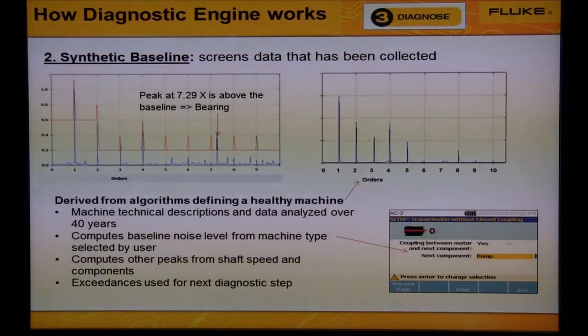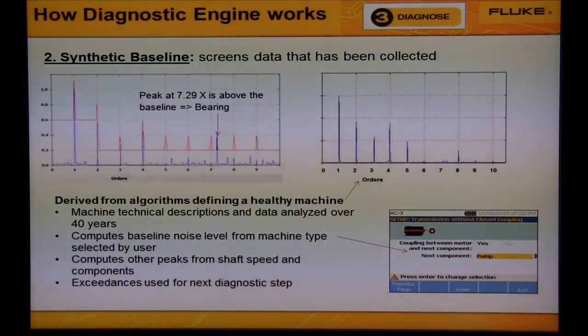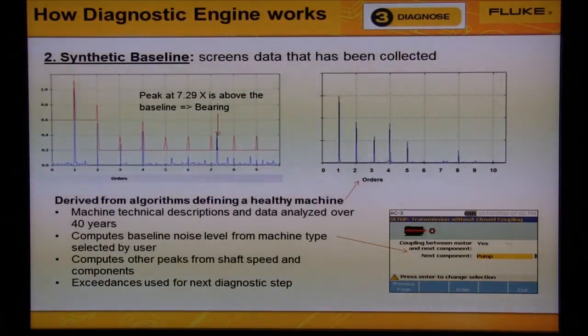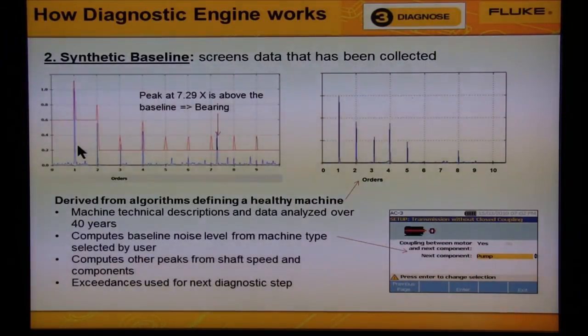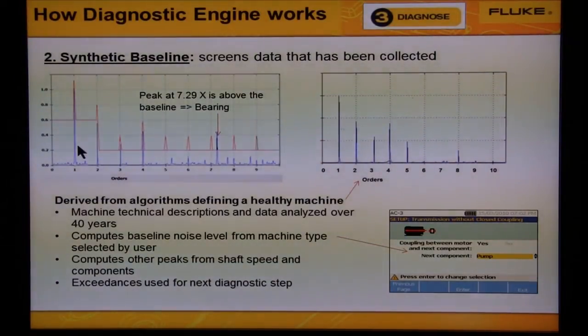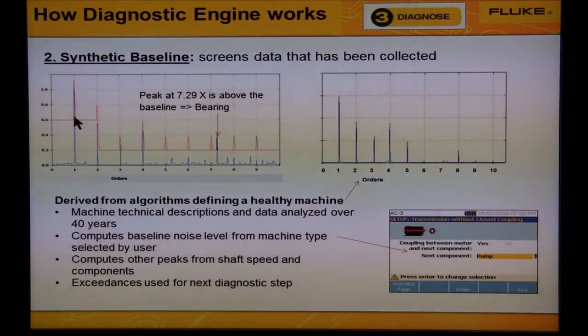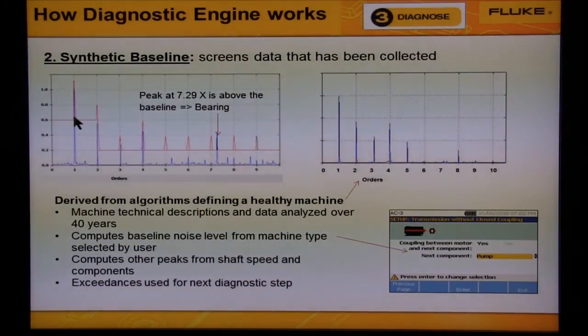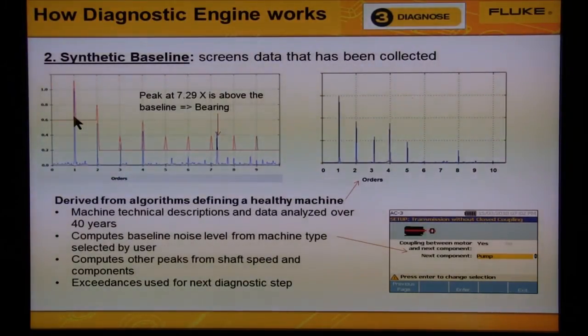In the graph on the left, we see a low red line that reflects the baseline level selected for this machine. Notice that in the lower frequencies, over to the left, the alarm level is higher because noise levels are higher in low frequencies. Also notice that the baseline level is raised to cover the peak at 1x, because we expect a larger vibration to be seen from the shaft vibration, which we found in the previous step.